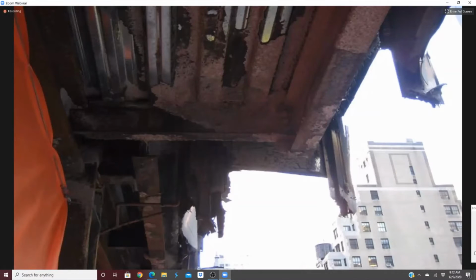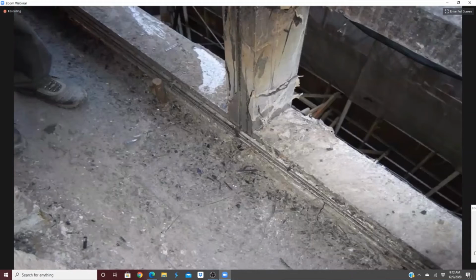On the floor where the fire broke out, you can see the failure of the wall system, which is exactly what will happen in a fire. The aluminum framing, vision glass, and spandrel panels are completely gone. But on the floor above, the anchor and the aluminum framing are all intact and protected. So in this case, the perimeter fire barrier system did its job.